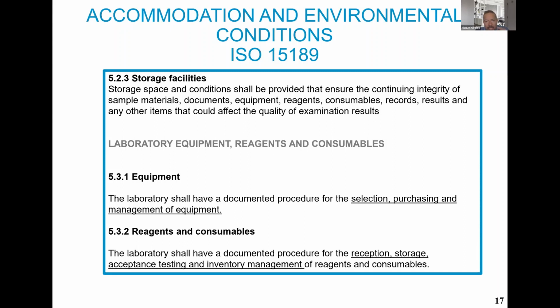And then I wanted to bring in ISO clause 5.3.1, just to keep in mind a little bit of what we just mentioned. It is on the ISO very clear that for equipment, we must have a documented procedure for the selection, purchasing, and management of equipment. So everything that I'm saying today is evidence-based, and you can find it on the ISO, and you can find it on other international guidelines, but these are the elements that we must keep in mind, and we must develop policies and procedures for each of these elements. When it comes to reagents and consumables, the ISO is telling us that we must have a documented procedure for reception, storage, acceptance testing, and inventory management of reagents and consumables.